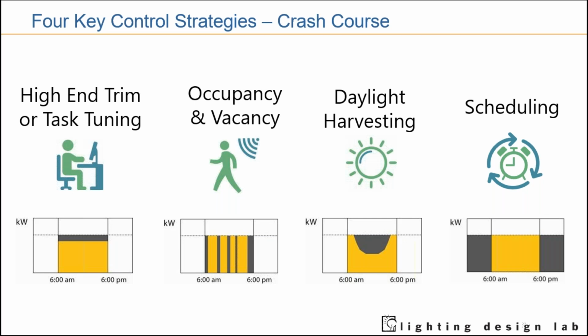Number one, because the fixture is not running at 100% capacity, there's a ceiling before the 100%, and that is being set depending on what's best for the space, depending on the required foot candles, the tenant comfort, and reducing glare. Because the light fixture will not be running at 100%, that extends the life of that fixture. There's going to be less heat, and as lumen depreciation starts hitting and the lights get slightly dimmer and dimmer, sure, you can adjust the high-end trim to allow more light and continue providing the correct amount of foot candles for your task.